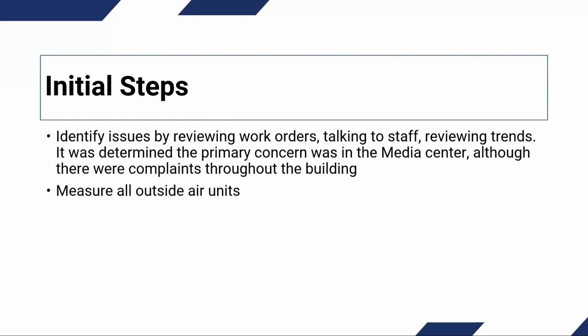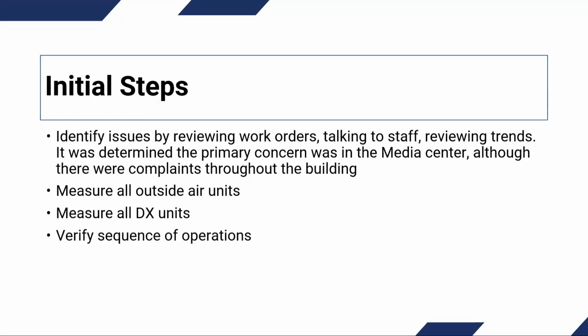So we measured all the outside air units. Again, even though we did the test and balance, we reread every outside air unit on the project to make sure the CFMs were correct and that the units were performing the way the manufacturer indicated it should. We measured all the DX units that served the media center and areas of concern. And then we went back through and we re-verified all the sequence of operations on the project. On this one, we also took some thermal scans of the building. We utilize thermal imaging cameras quite a bit for troubleshooting procedures. If you don't use them in your trade, whether you're commissioning or test and balance, we highly recommend it. It's not hard to get a thermography certificate, and it's very beneficial when trying to troubleshoot things.